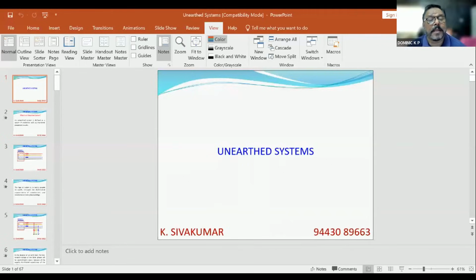So, question from Smruti Pradhan. For a DG set installed for temporary power supply, we need not earth its neutral and can run it as an unearthed system? I am very sorry, the perception that we need not earth it is wrong. The moment you have a voltage above 250 volts, as per the CEA regulation, as per IS 732 and Indian Standard 3043, you must earth, temporary or permanent. You must earth the DG set. There is no question of an unearthed system.